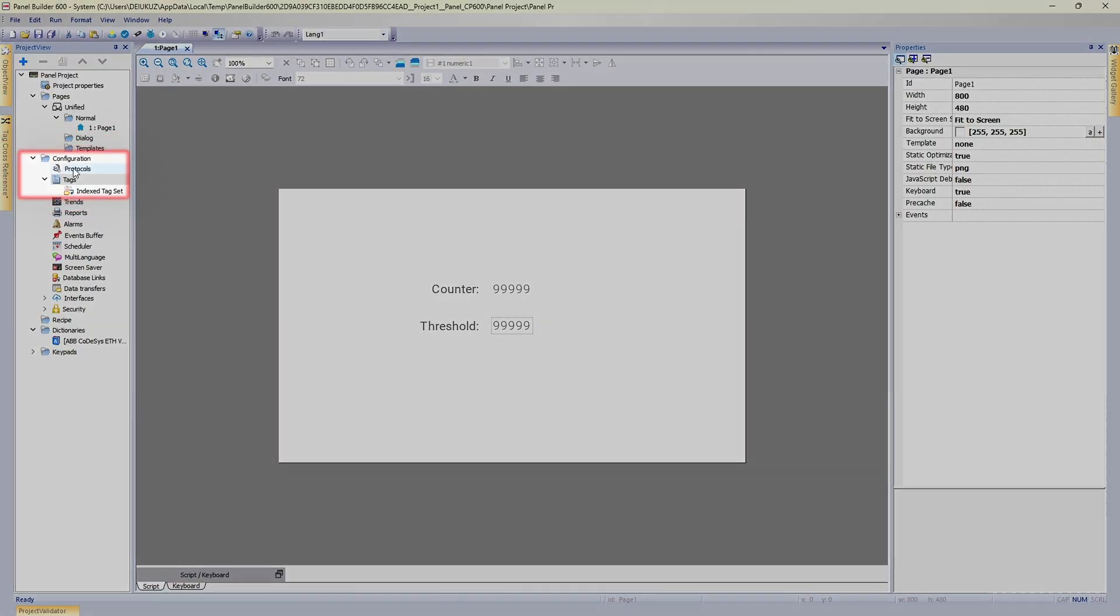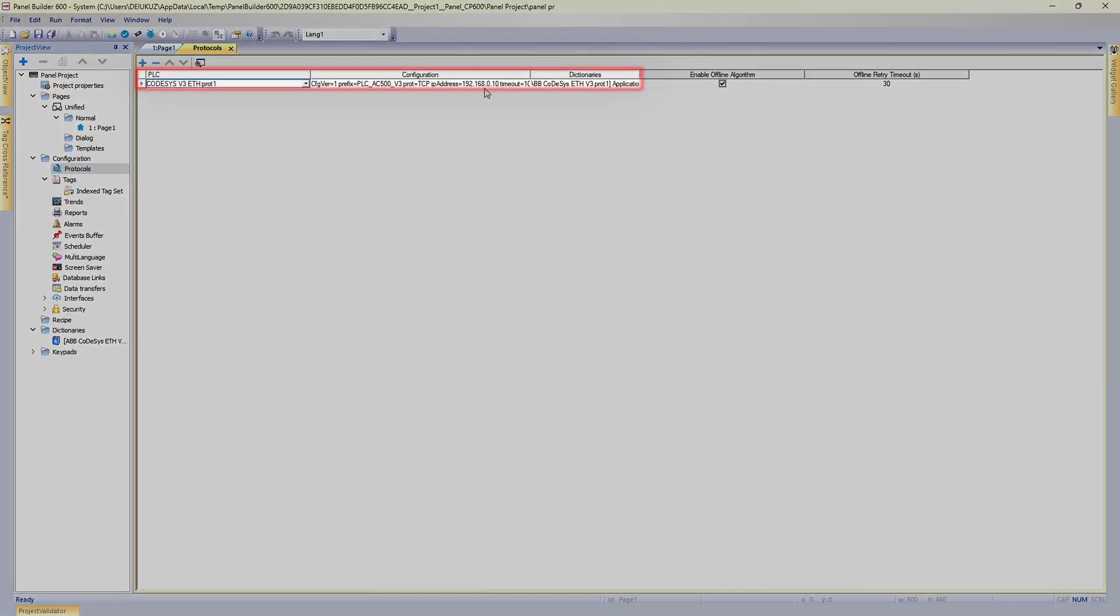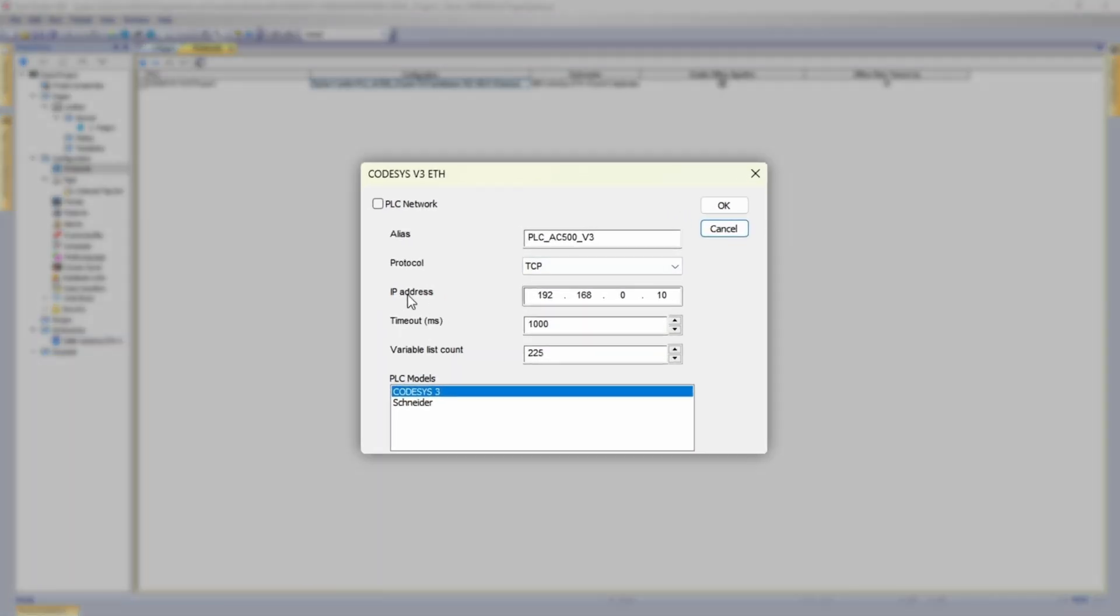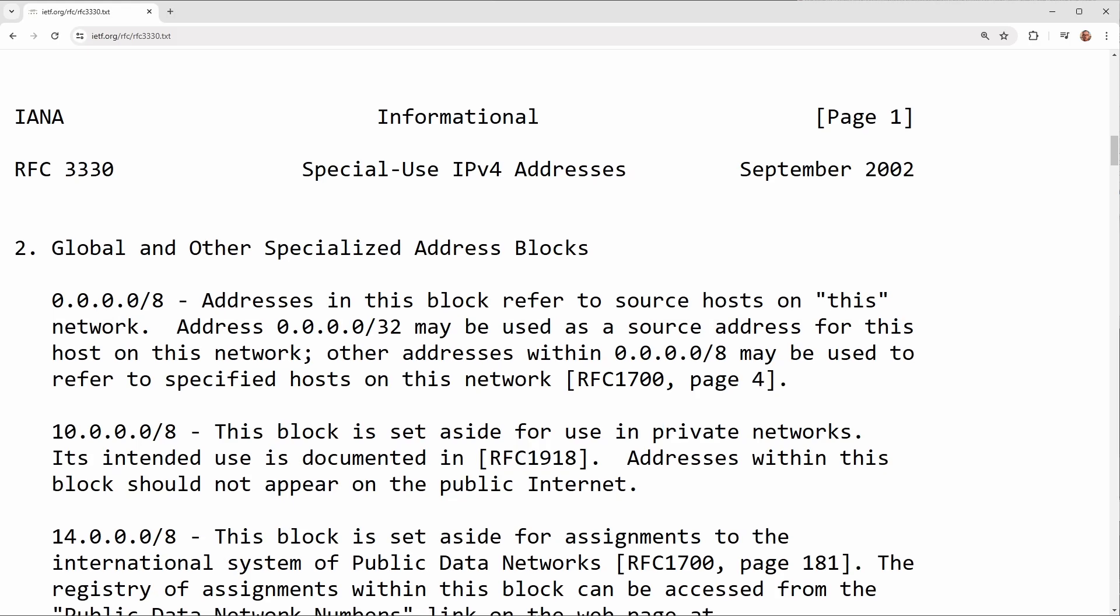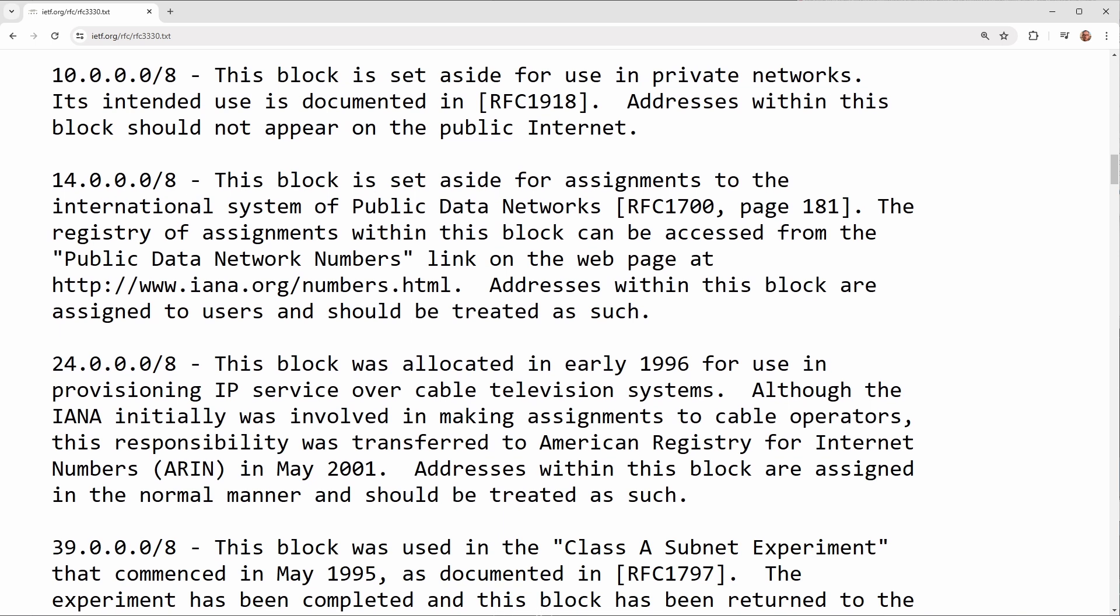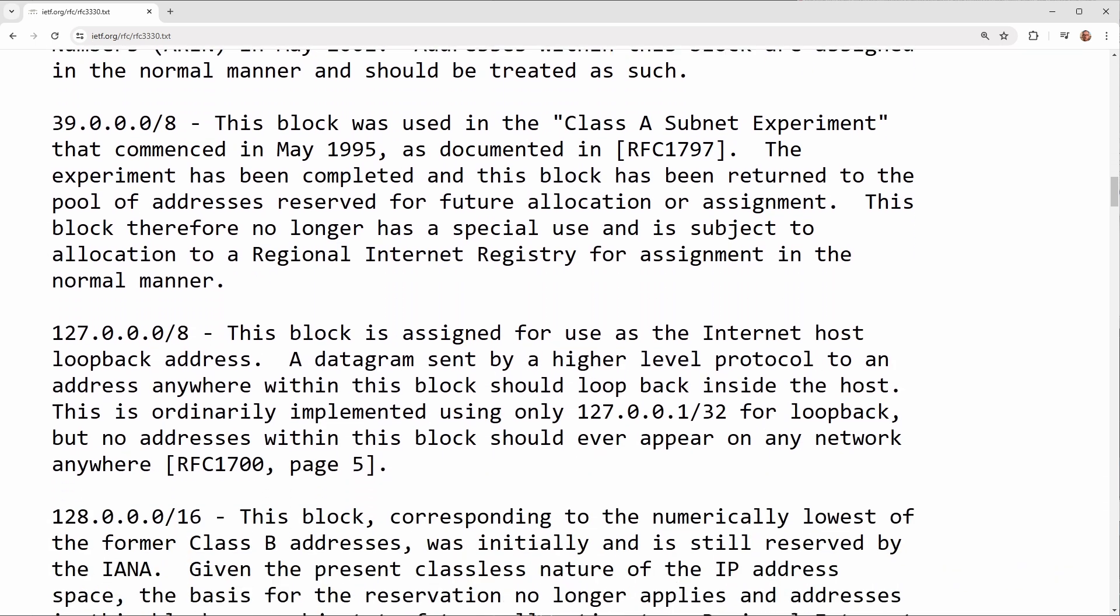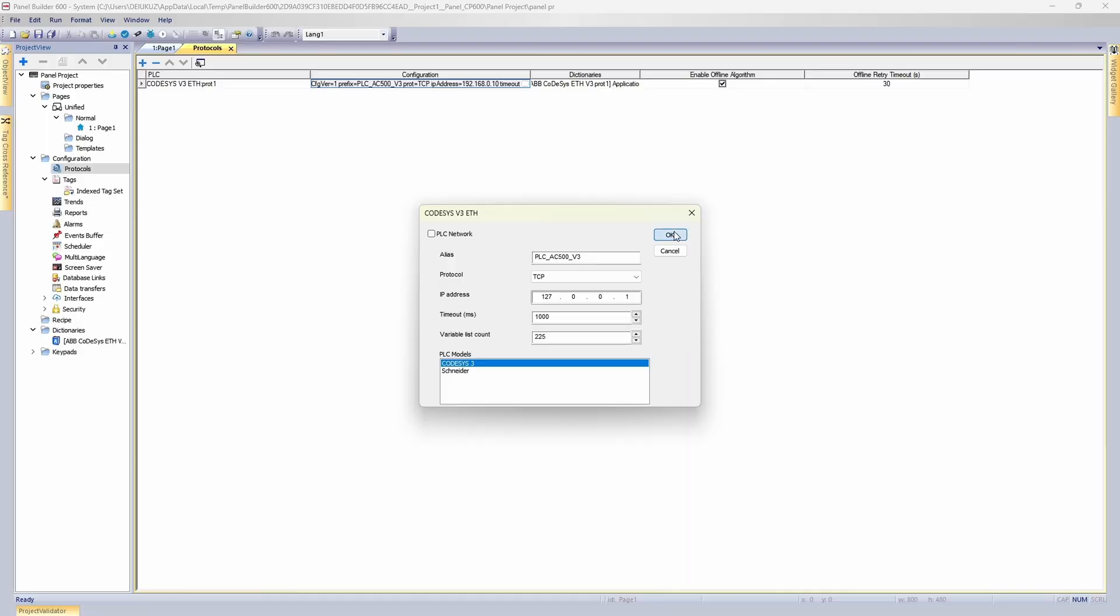Here's a trick which will make the HMI simulator connect to the PLC simulator. We head to Protocol section. Here is automatically created Codesys V3 driver with a simple configuration as a dictionary. We click to Configuration and instead of PLC IP address, we put loopback adapter IP 127.0.0.1. In case you don't know what loopback IP is, it's just a fancy way to tell one application to connect to another application on the same computer.